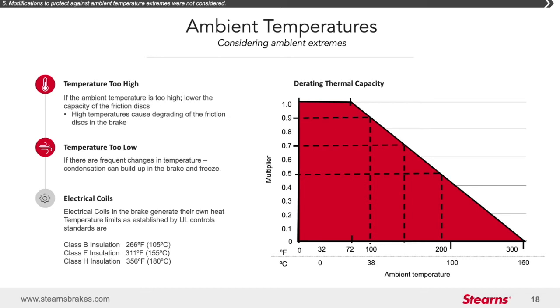Coils, because they are electronic components, generate their own heat and have their own temperature rise. It's because of this you have to factor in the temperature rise of not only the coil itself, but also the temperature of the environment in which it operates. For example, let's say the coil temperature rise is 200 degrees and it operates in an environment that is consistently 80 degrees. You need to take the 200 plus 80 and you've already exceeded the limit for Class B.